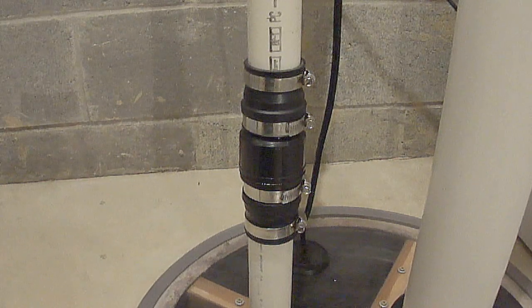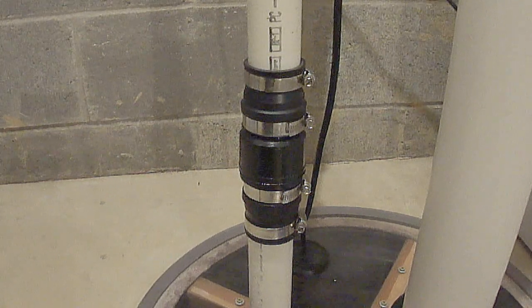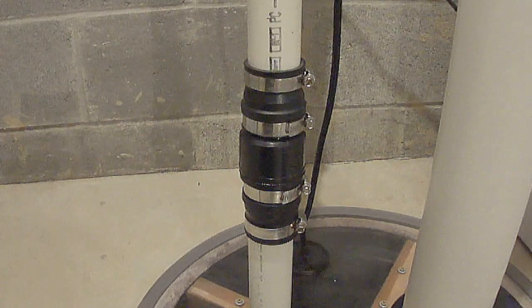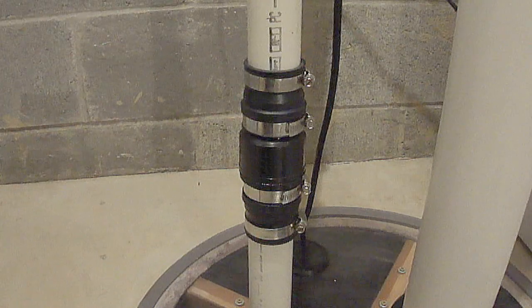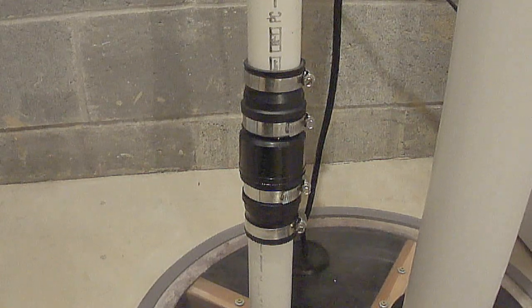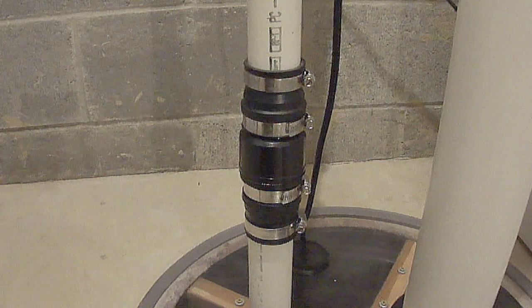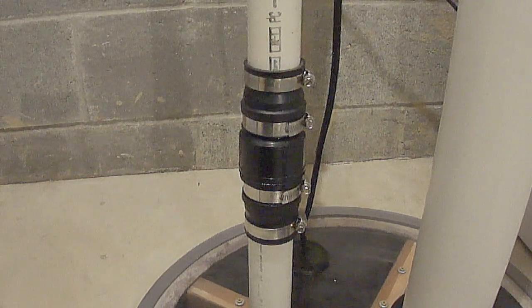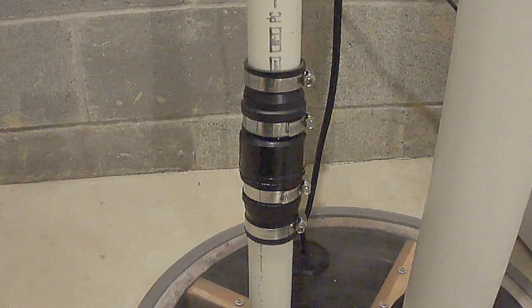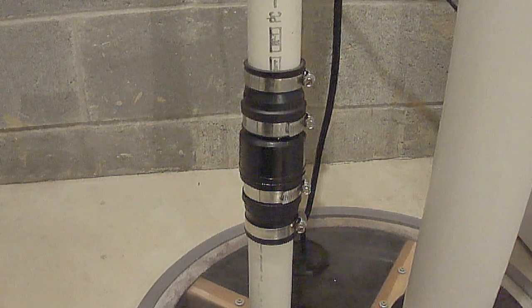So the first thing I did was I went outside just to make sure that the discharge pipe was discharging the water from the sump pump properly and that nothing was blocked — and it was all fine. So I came back inside, and what the system does is when it kicks on and then turns off, you'll get this hammering, clattering noise just like that.